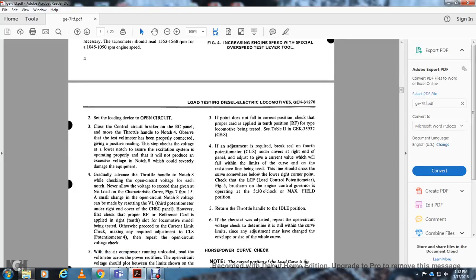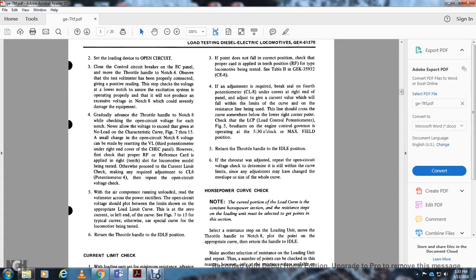Observe the voltmeter, which has been properly connected to give a positive reading. Check whether the voltage lies within range at the lower notches. Ensure the excitation system is operating properly, so that it will not produce an excess voltage at notch 8, which could cause severe damage to the equipment.